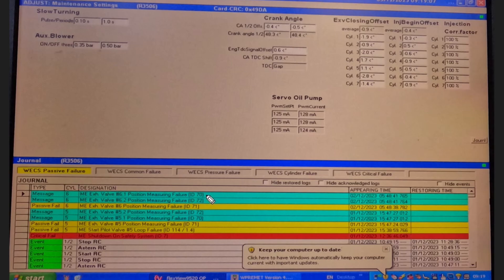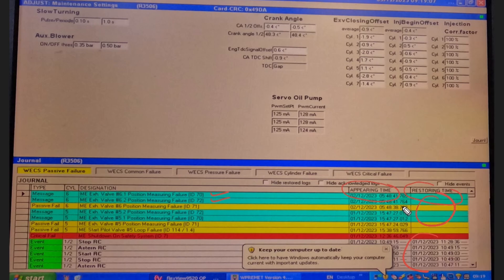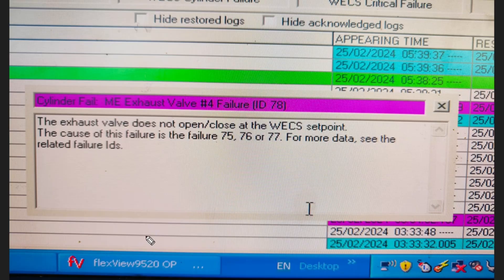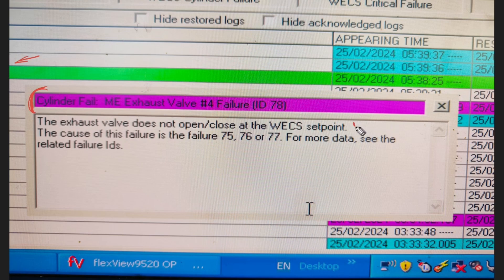On this image you can see messages for alarms or any failure available in your main engine. You can double-click on an alarm and a troubleshoot option will appear, showing the appearing time and restoring time of the alarm. Some alarms are restored and some are not. Once you double-click, it will guide you to check the particular issue. These troubleshoot guide options will be shown to help you diagnose the problem.